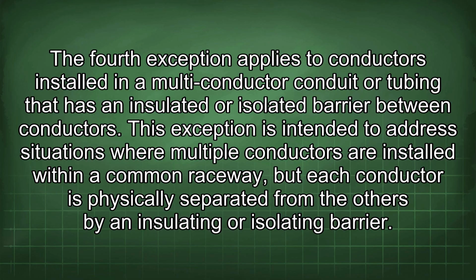The fourth exception applies to conductors installed in a multi-conductor conduit or tubing that has an insulated or isolated barrier between conductors.